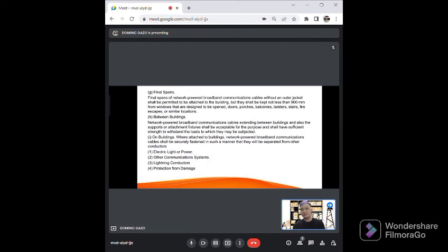And for over pools, clearance of network powered broadband communications cable in any direction from water level, edge of pool, the base of the diving platform, and anchored raft. For the above pools, the vertical clearance shall be not less than 2,400 millimeters from all points of pools. And we have final spans. These final spans, the outer jacket shall be permitted to be attached to the building, but shall be kept not less than 900 millimeters from windows. And these are designed to be opened, doors, porches, balconies, ladders, stairs, fire escapes, or similar locations.